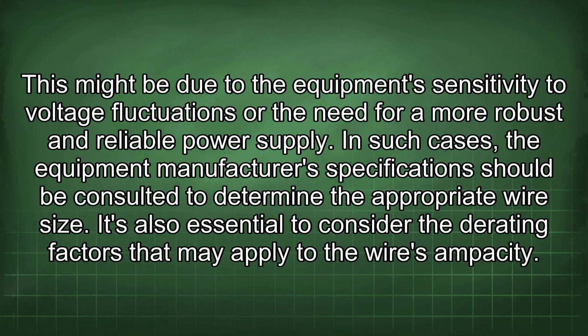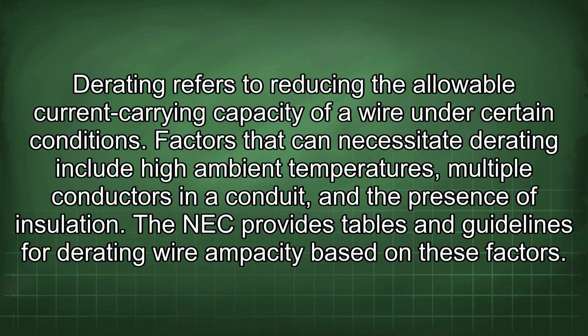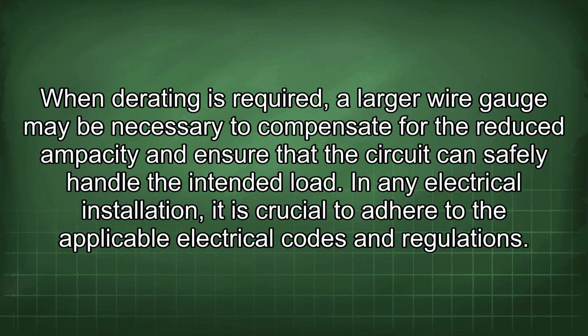It's also essential to consider the derating factors that may apply to the wire's ampacity. Derating refers to reducing the allowable current carrying capacity of a wire under certain conditions. Factors that can necessitate derating include high ambient temperatures, multiple conductors in a conduit, and the presence of insulation. The NEC provides tables and guidelines for derating wire ampacity based on these factors. When derating is required, a larger wire gauge may be necessary to compensate for the reduced ampacity and ensure that the circuit can safely handle the intended load.